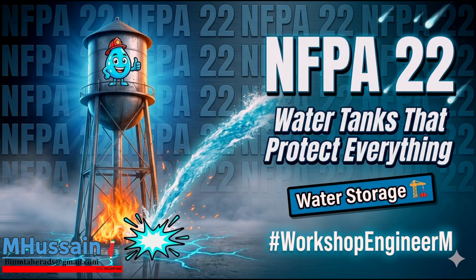Oh, wow, so it's physically eating away the metal. It sounds like a handful of gravel has been thrown into the pump casing. Within minutes, cavitation will erode the impeller to the point where it can no longer generate the required discharge pressure. So the pump is running, the motor is screaming, but no water is reaching the fire. A total system failure. So the engineering challenge is, how do you stop a vortex from forming in a tank holding hundreds of thousands of gallons of moving water? The standard mandates a vortex plate assembly, often called an anti-vortex plate.